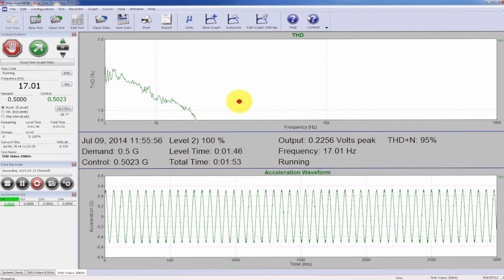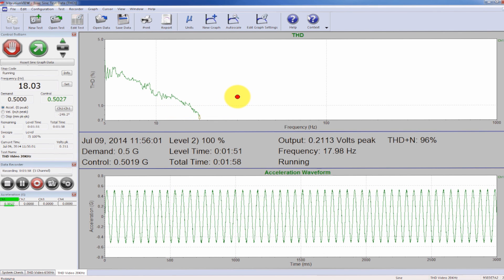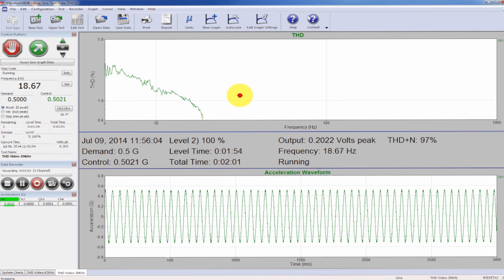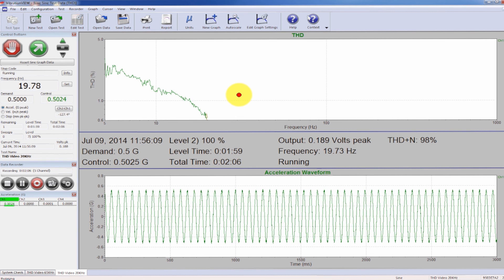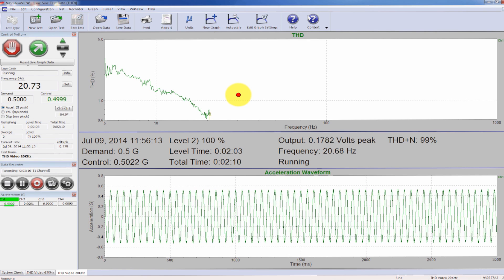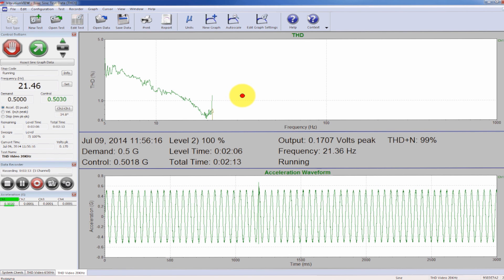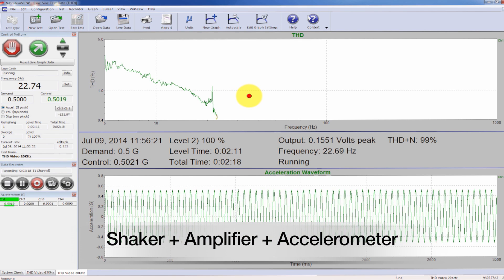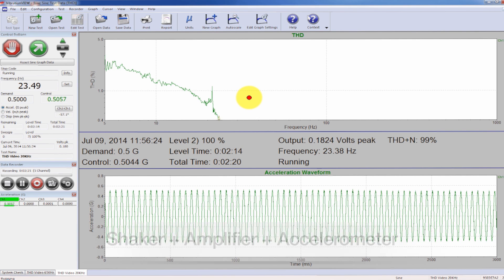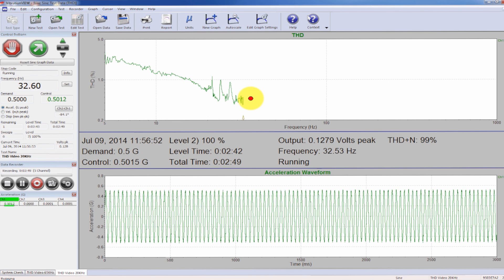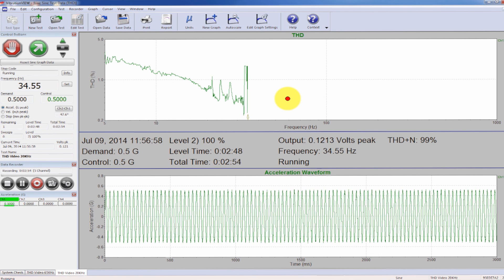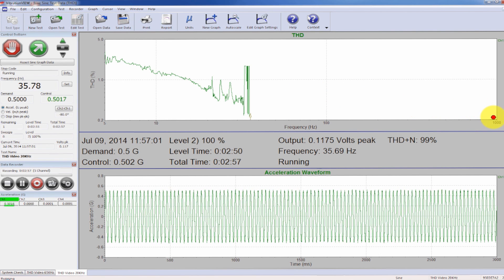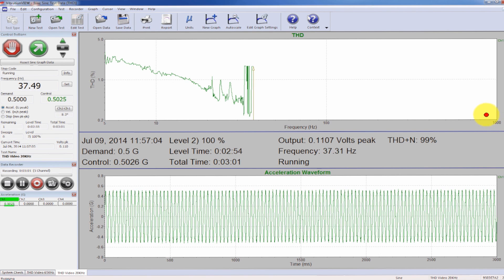You can see we're dropping below 1%. And I would say if you have a system with 1% THD, that's a very good system in terms of distortion. It's also important to remember that the distortion that we're measuring is cumulative for the system as a whole. So it's not just the shaker, but the amplifier and accelerometer are coming into play here as well. I believe the first resonant point of this system is going to be actually outside of our frequency range that we're operating at.